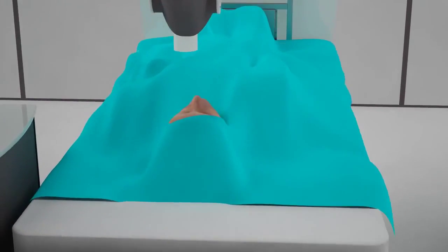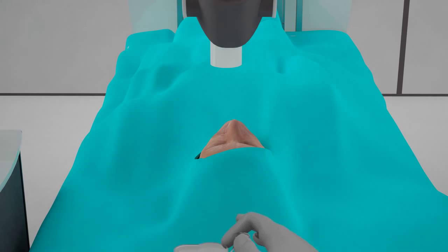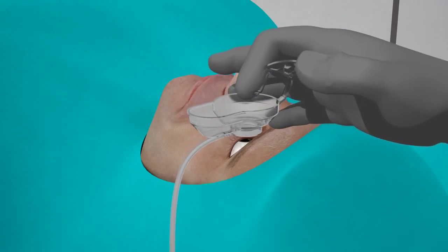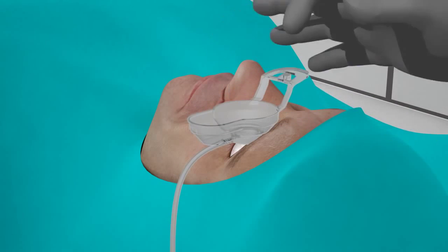The unique and intelligent design of the Femto LDV Z8 handheld system allows for a completely different docking procedure. First, a suction ring is easily placed on the patient's eye.